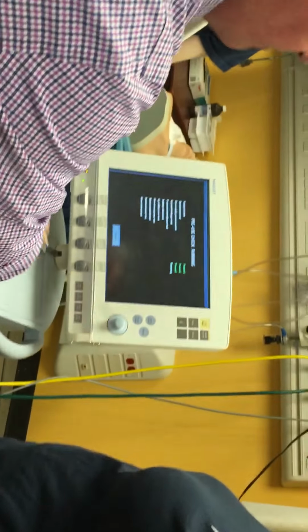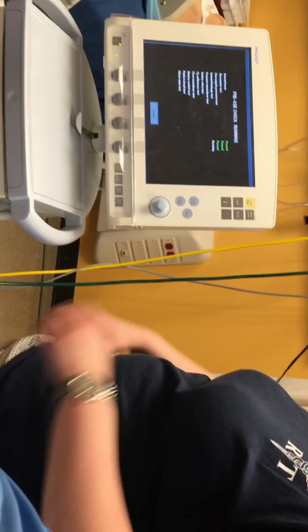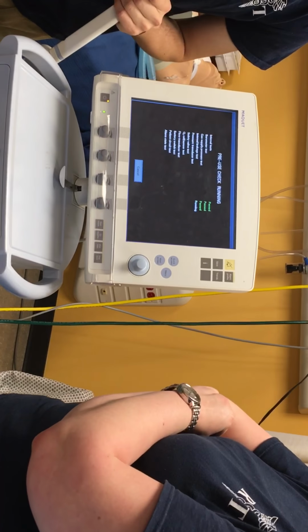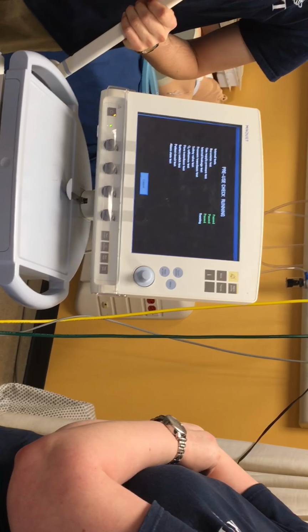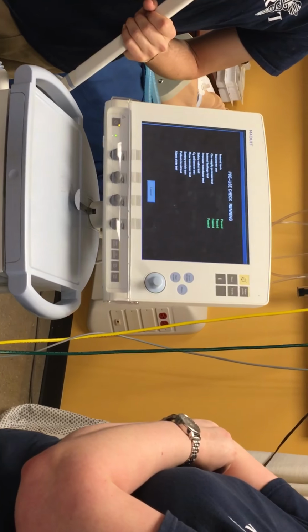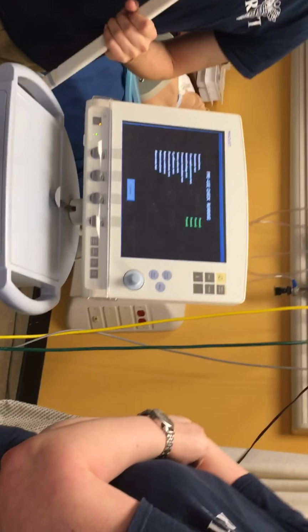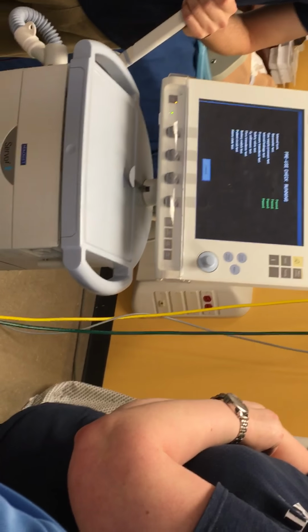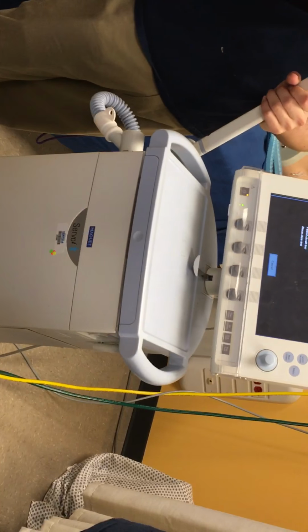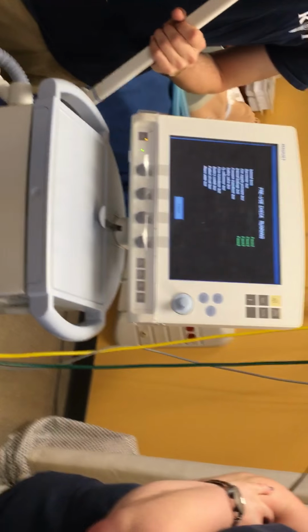If you listen, you're going to hear a bunch of solenoid valves opening and closing and gas shuffling through here. It's testing the internal valves and stuff. And that's what it's doing. If you ever open up one of these ventilators, all it is, is tubing and solenoid valves. That's it.